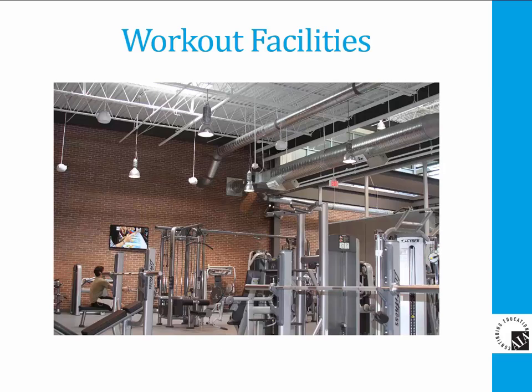The outlets in this workout facility are mounted at an angle to direct the air toward the occupants. While I would not recommend this for stationary or sedentary occupants, for this facility where metabolic rates are higher during exercise, it is an acceptable arrangement.